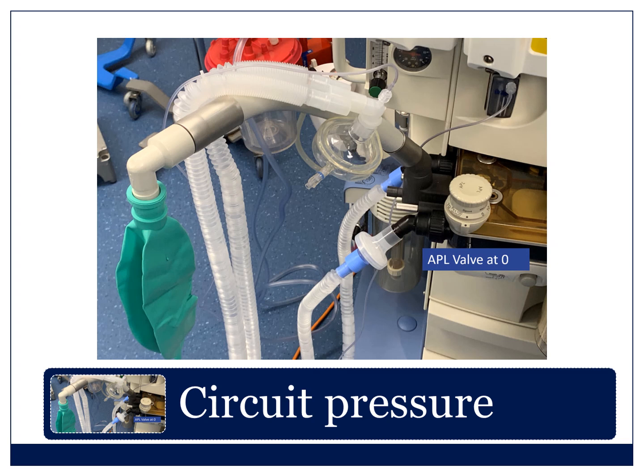It's testing there's not a massive leak. It's testing that there's gas coming out of your machine. It's testing you know how to use an APL valve, and it's testing that you can ventilate the patient. So that little test, just before I put it on a patient's face, I check that I can generate pressure, I open the APL valve, and I put it on the patient's face. And if you do that, there are so many things you're testing with that little maneuver. You've done more than half of an anesthetic machine check just by what I've told you so far.